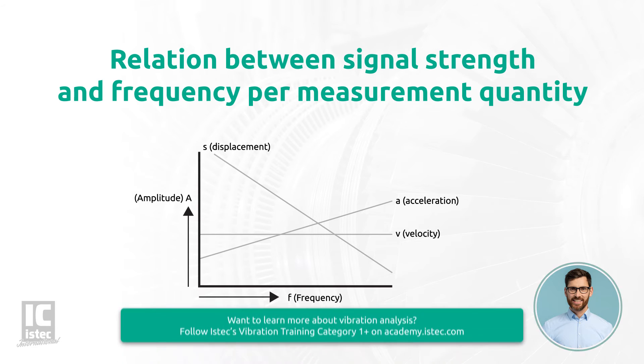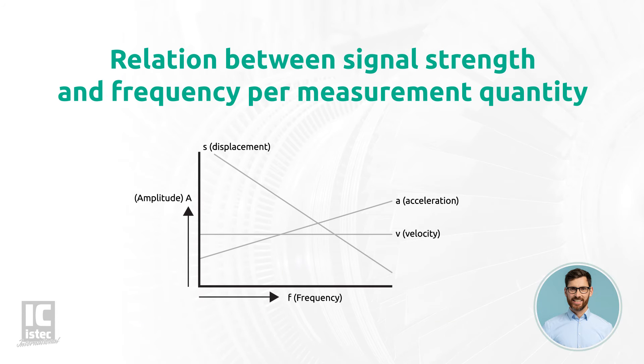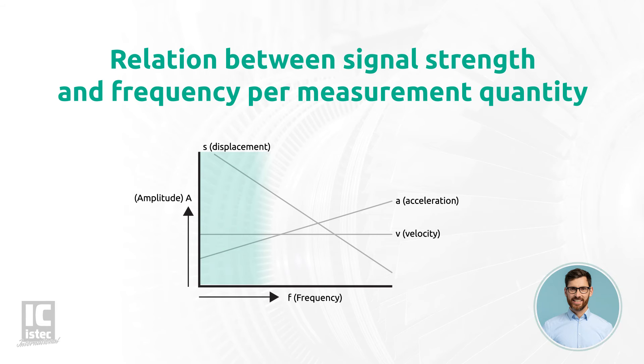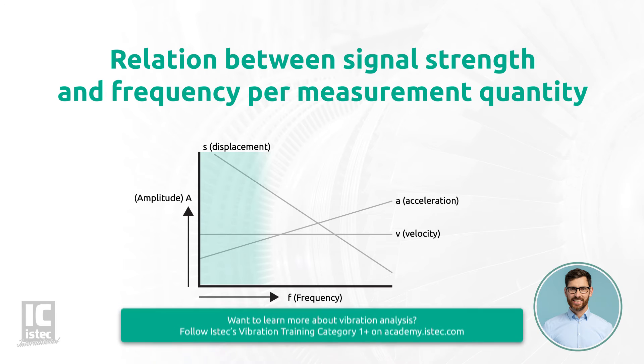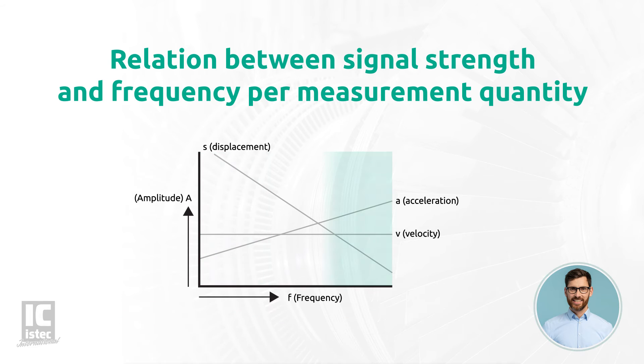Again, S, V, and A represent the measurement quantities displacement, velocity, and acceleration. F is the frequency. The vertical axis represents the amplitude A. We can see that for measurements on low speed applications, it is best to use the measurement unit displacement. The amplitude A of the displacement signal is highest at low frequencies. For measurements on high speed applications, it is best to use the measurement unit acceleration. The amplitude A of the acceleration signal is highest at high frequencies.